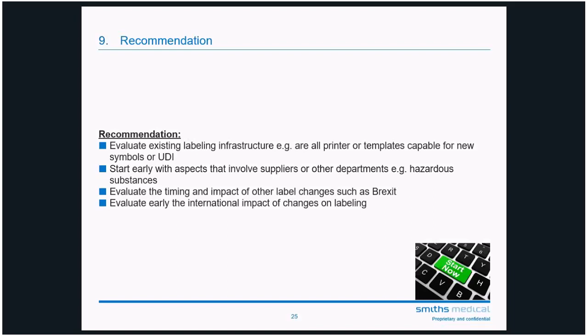So have you run through your device risk management? The ones that have a combination of a high likelihood and a strong severity are the ones to consider. So have a review of your risk management file, and that's what I have mentioned in the summary as well. There is a stronger focus from the MDR on consistency, and that requirement is one facet of that consistency approach from risk management towards labeling.